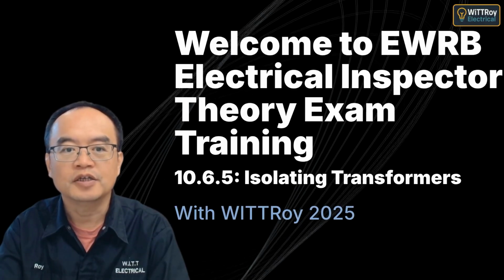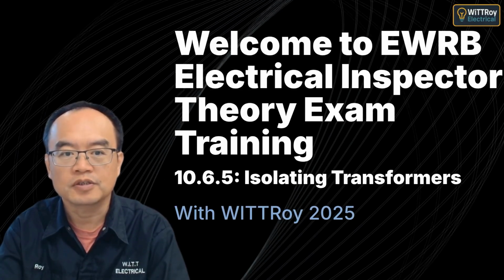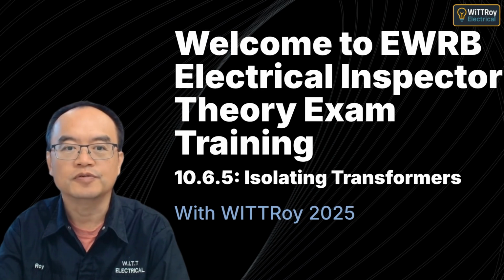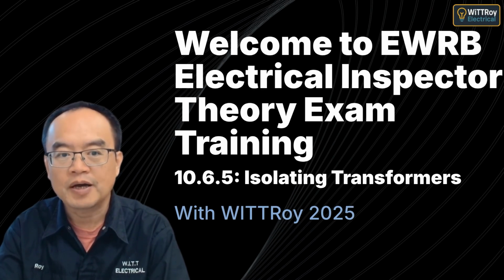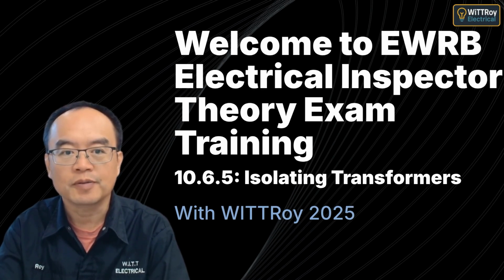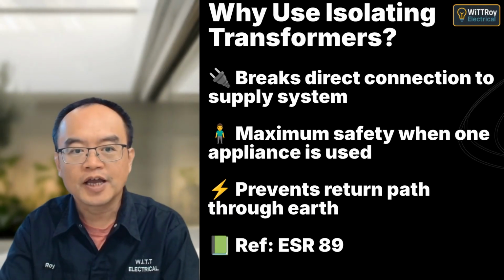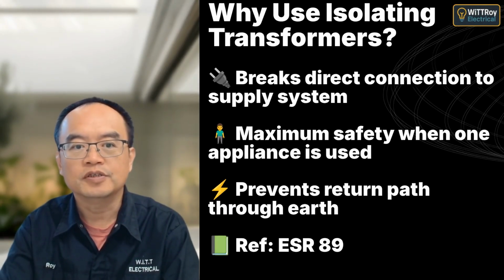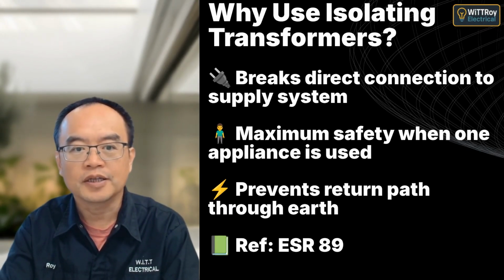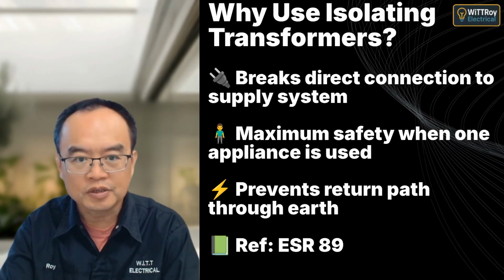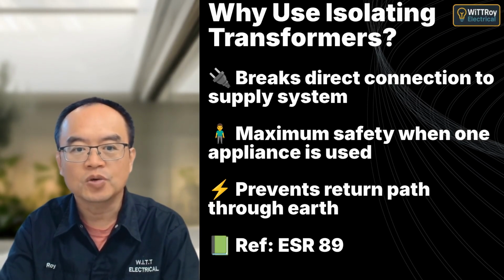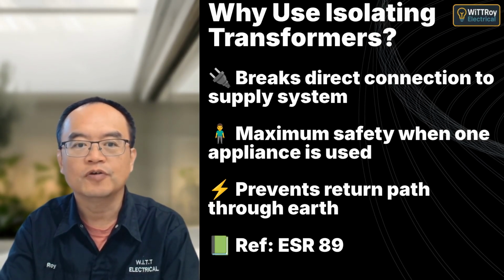In this short lesson, we're looking at isolating transformers, what they do, why they improve safety, and how they're used with appliances, especially in special environments. An isolating transformer separates the supply from the appliance, eliminating a path for shock current through earth. It provides maximum safety when only one appliance is used. There's no fault return path.